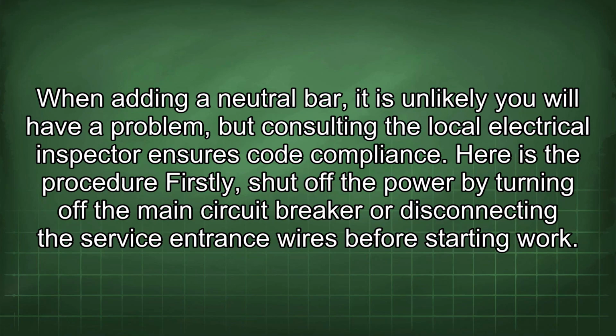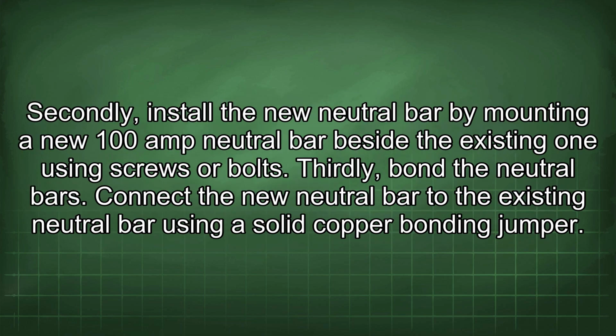When adding a neutral bar, it is unlikely you will have a problem, but consulting the local electrical inspector ensures code compliance. Here is the procedure. Firstly, shut off the power by turning off the main circuit breaker or disconnecting the service entrance wires before starting work. Secondly, install the new neutral bar by mounting a new 100 amp neutral bar beside the existing one using screws or bolts.